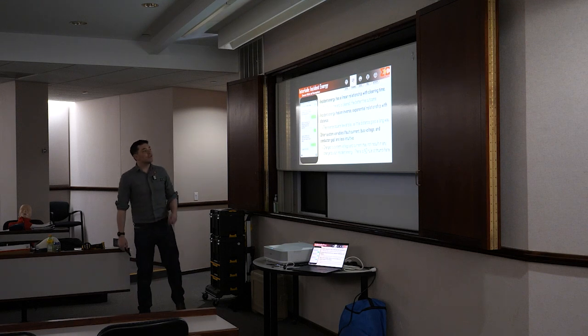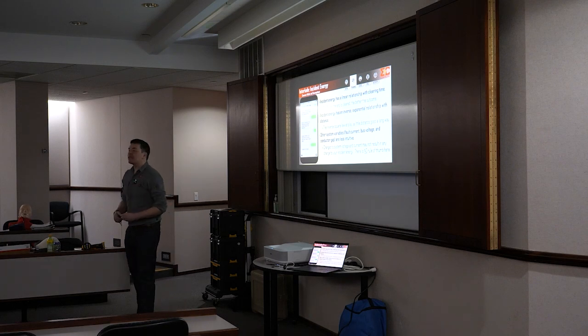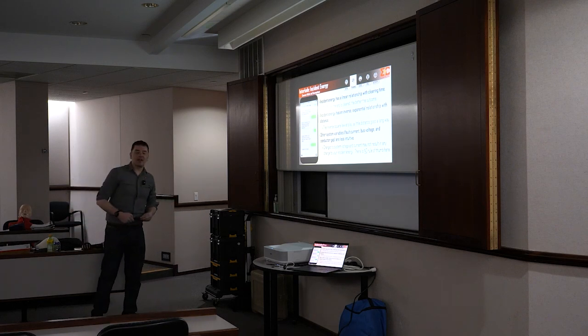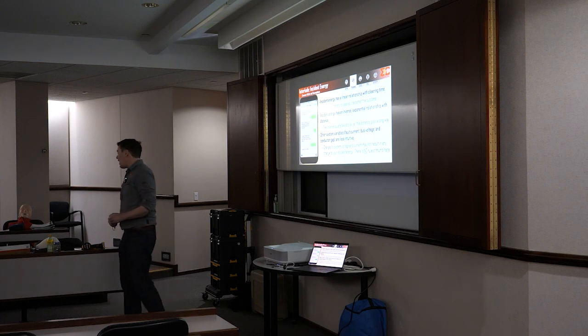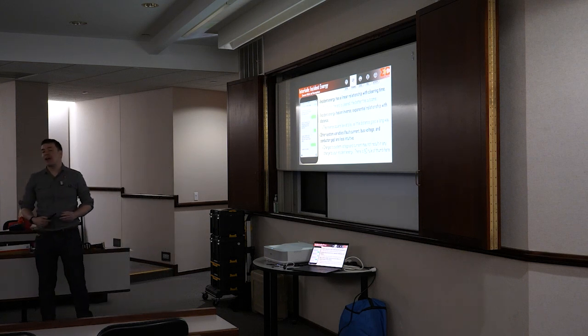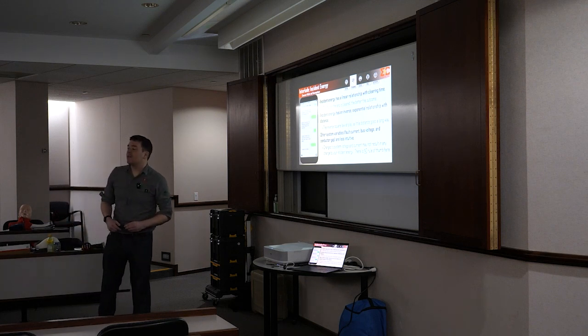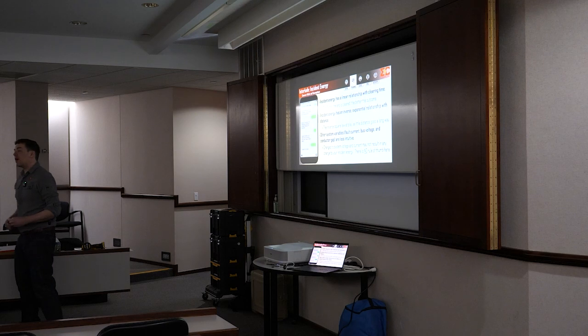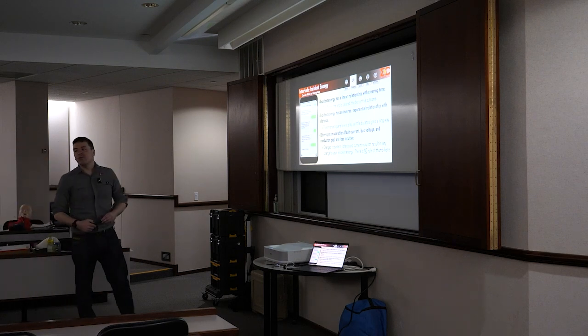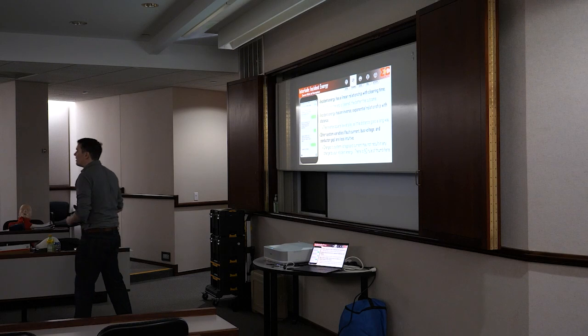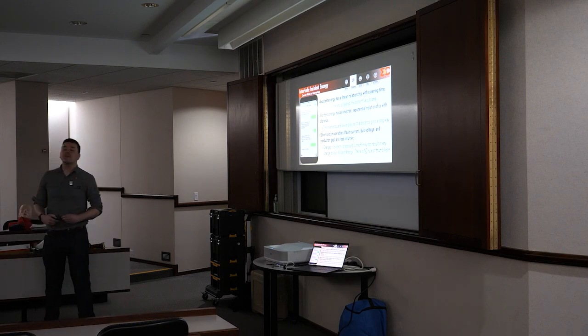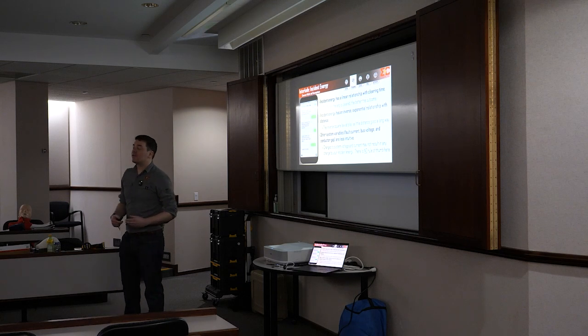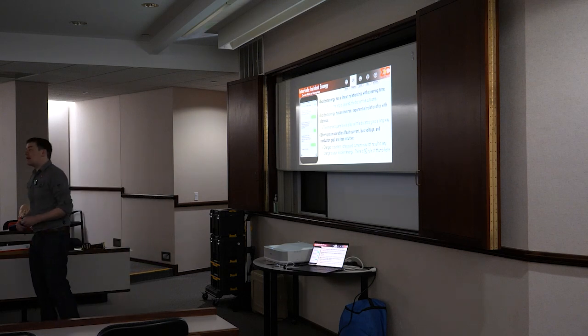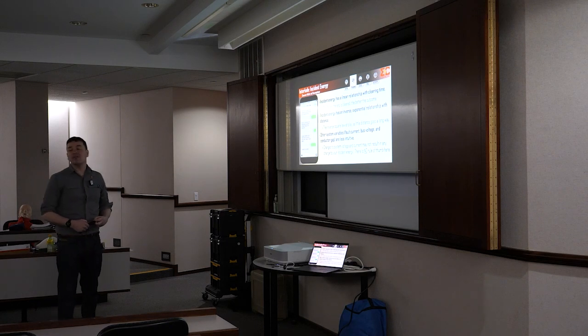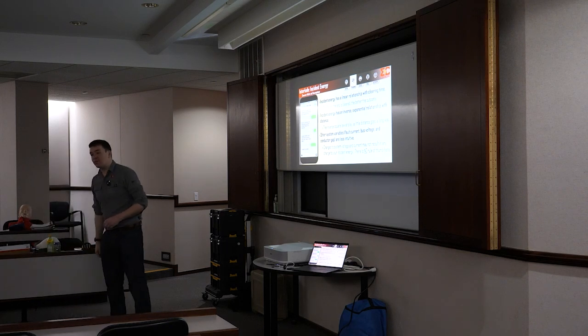And then finally, other system variables, for example, fault current, bus voltage, and conductor gap, do have an impact, but are less intuitive. You cannot necessarily say a 480 volt system has a lower or higher fault current or arcing fault current and/or incident energy than a 15 kV system until you understand just how much current is available and what the operating devices are. There is no rule of thumb, even though lower voltage, higher current systems will more often have greater amounts of incident energy that you have to potentially contend with. Ultimately, when in doubt, look for every opportunity to mitigate or eliminate the hazard by de-energizing the system while you're doing that work.